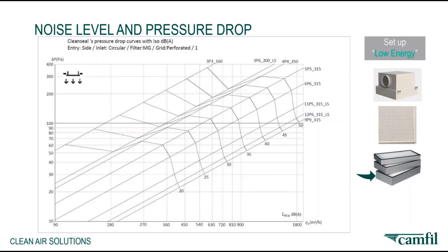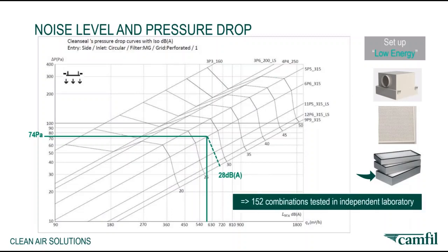This is basically the graph you will get with different housing sizes on the right. Taking an example for a 6x6 housing, side spigot, 315, perforated front plate, and a 110 mm H14 filter. So for a nominal airflow at 0.45 meter per second, the pressure drop is 74 Pascal, which is relatively low, taking into consideration the pressure drop of the filter. And this configuration generates a 28 dBA noise level as well, relatively low. So this information is available for 152 different setups. Contact your local CAMFIL person to get access.